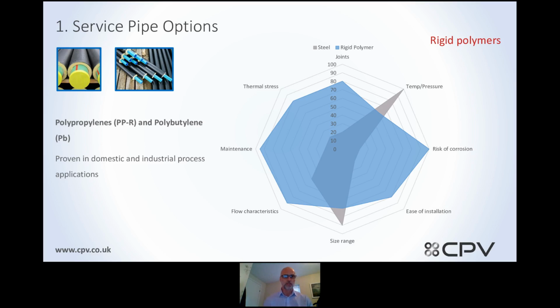The next systems I'm going to discuss are rigid polymers. Aquatherm did a presentation earlier on polypropylene systems, proven in domestic and industrial applications. Again, risk of corrosion is not a problem. On ease of installation, these systems are heat fused, so electrofusion or butt welded in situ. There are training courses available for those applications. Again, they'll take low temperature, 82. They will take short bursts at higher temperatures, so that's something else to consider. Typically 6 and 12 metre lengths, so you are introducing more joints into the system compared with the coil systems, but then the size range does have an effect because these systems will go onto bigger sizes, particularly from 25 millimetre up to about 500 mil.